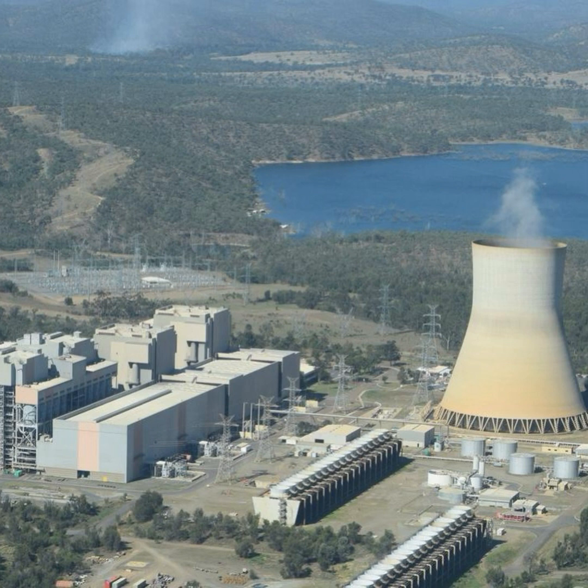The basic Rankine cycle of a thermal-electric plant consists of 4 stages in a continuous sequence. Heating of the fluid in question until it's a gas, expansion of the gas in a turbine creating rotation and performing work, condensation of that vapor exhaust from the turbine back into a liquid, and pumping or return to the heating stage, since it is unfortunately not possible to pump gas, though you can pressurize it and make it flow, but that's another story, thermodynamics and all that.